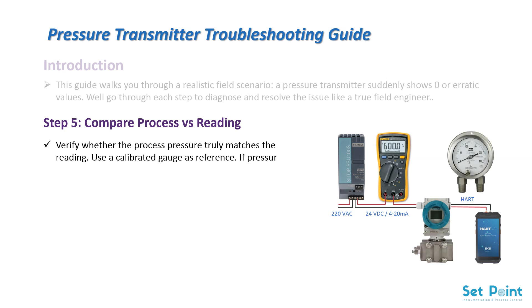Step 5: Compare process versus reading. Verify whether the process pressure truly matches the reading. Use a calibrated gauge as reference. If pressure exists but the transmitter shows zero, sensor damage is likely.